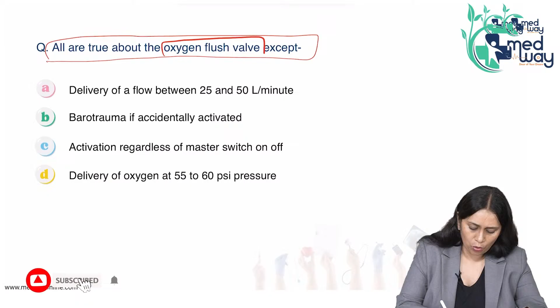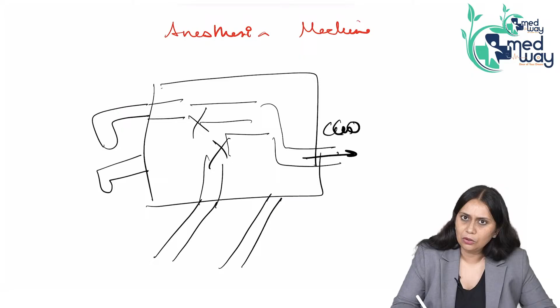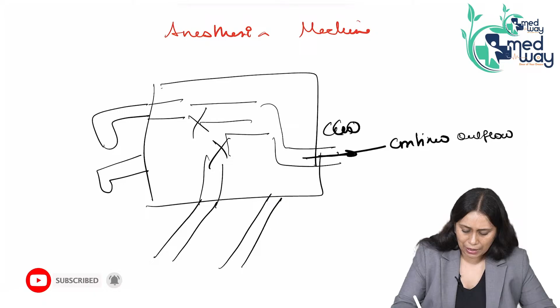So, what is an anesthesia machine? It is a device or an equipment which accepts the gas from the source. What are the sources? Gas cylinders and the gas pipeline. So, it accepts the gas from the source, then it reduces the pressure of the gas, mixes the gas in the required concentration and delivers the gas to the patient through the common gas outlet of the machine continuously. So, continuous outflow of gas happens from the anesthesia machine, right?